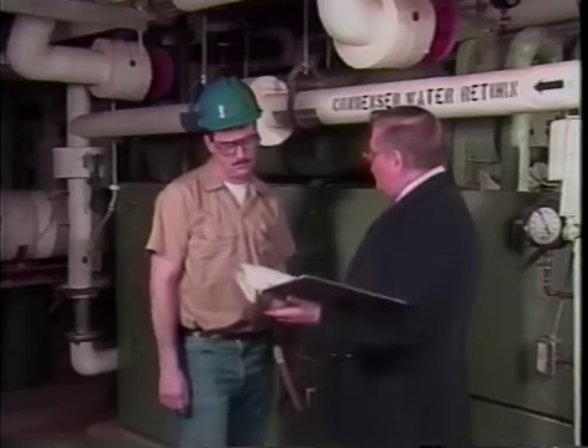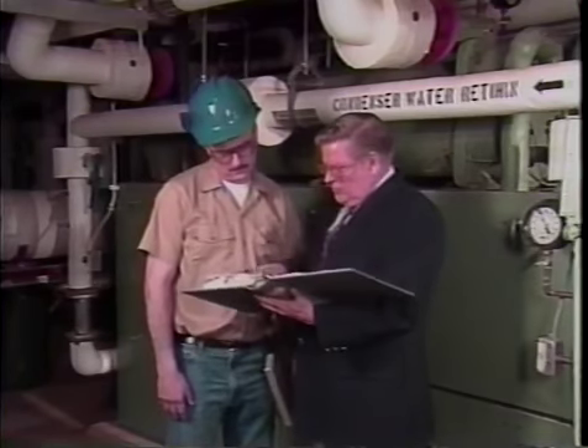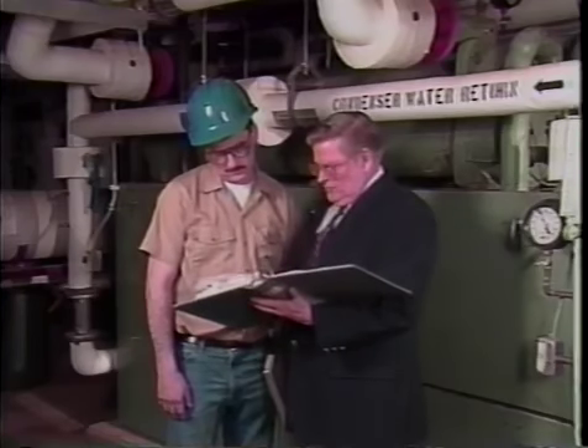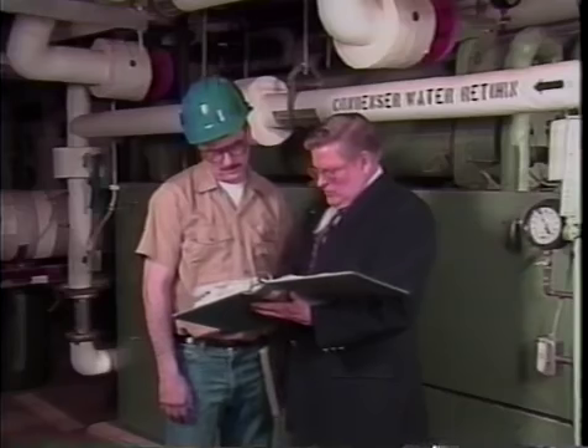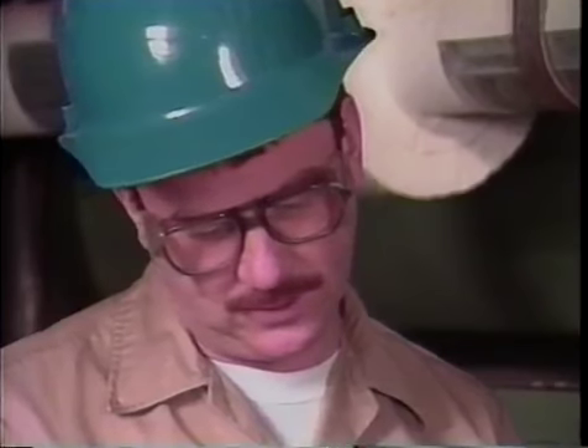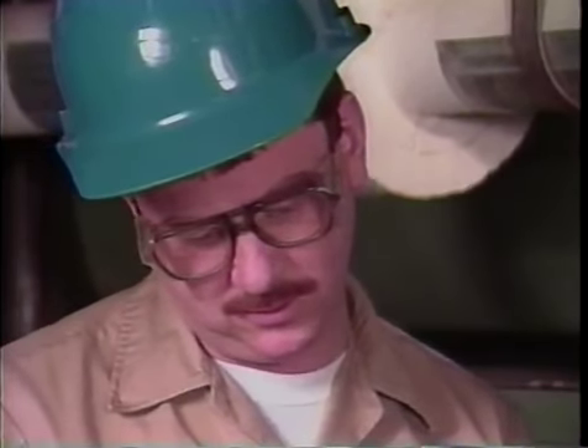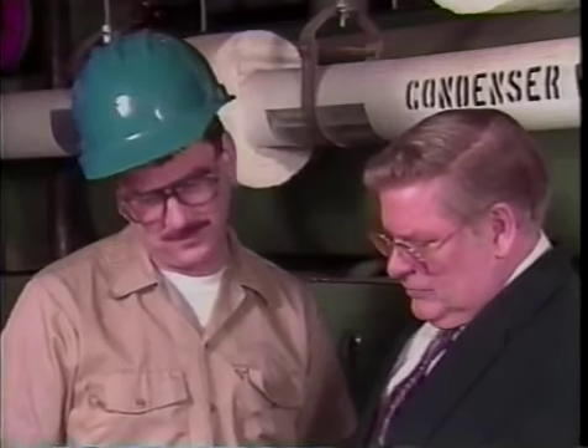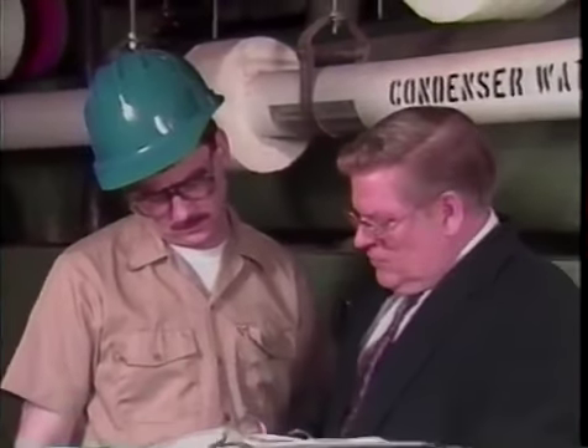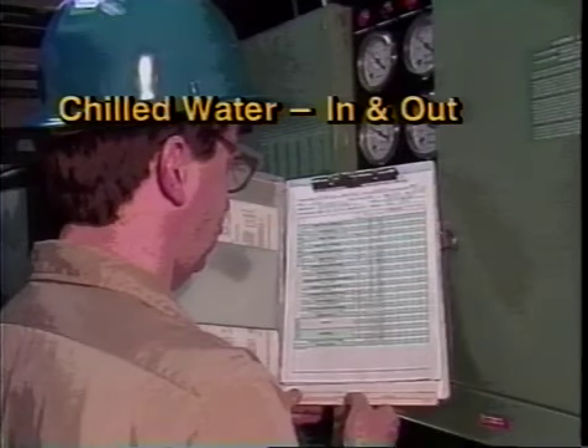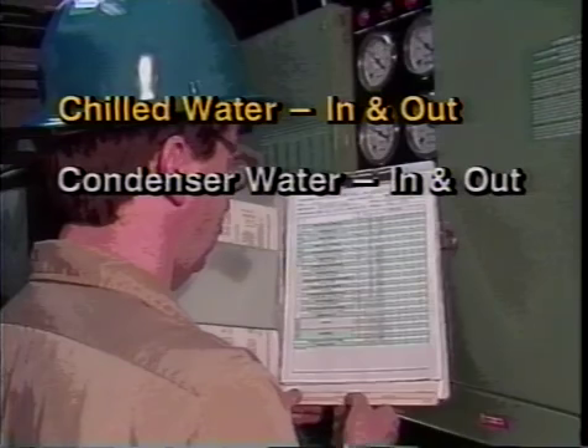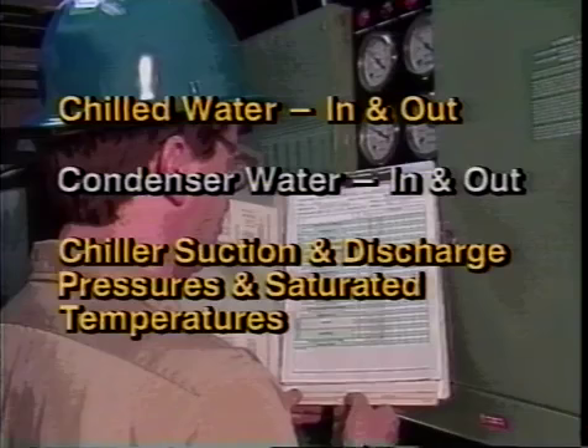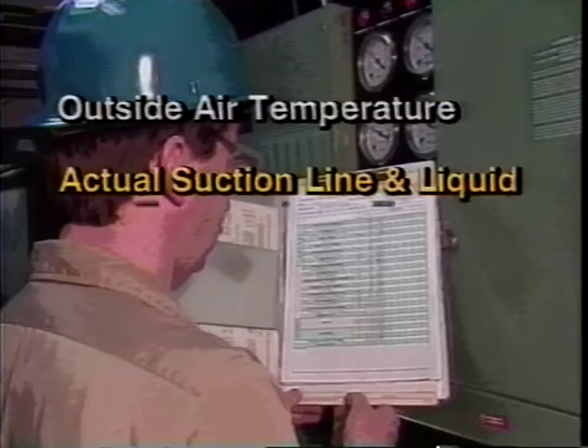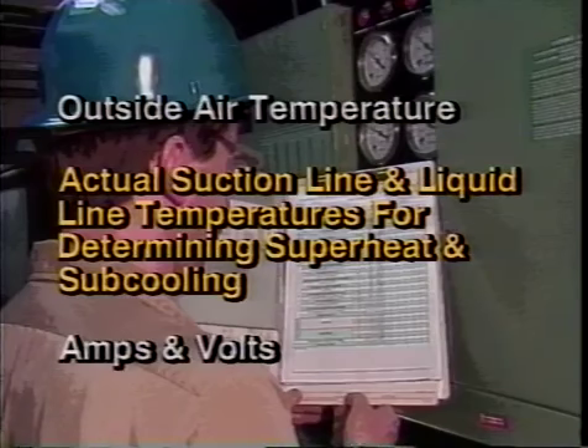You should be able to find past log sheets on the job site. If no log exists, then a log sheet should be started. When starting a new log sheet, you will need to record the design conditions of the chiller. This design information should be available either at the job site or from the manufacturer's representative, such as the local distributor or dealer's office. If you cannot get design data, then use the data taken on the initial startup of the chiller as a reference. You will also need to record the actual operating system temperatures and pressures. For example, chilled water in and out of the cooler, condenser water in and out of the condenser, chiller suction and discharge pressures and temperatures, outside air temperature, suction and liquid line temperatures, and finally, amps and volts.